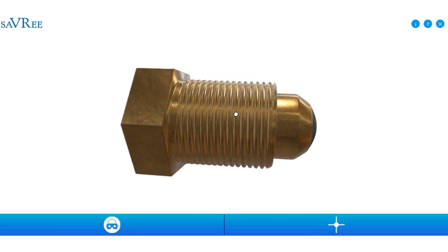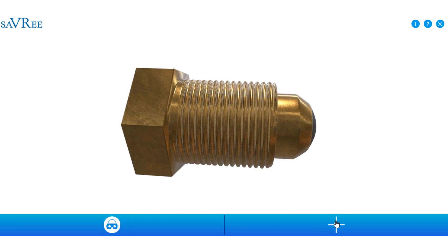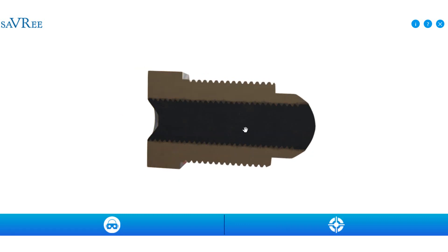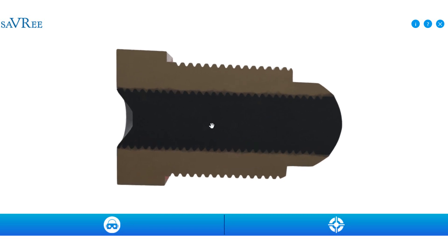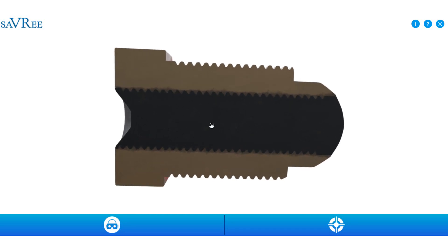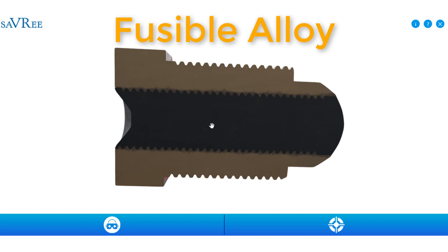Let's just take a cross section and see. The black gray area runs through the entire plug body. Now, the black gray area is actually referred to as a fusible alloy. It has a lower melting point than the plug body itself.